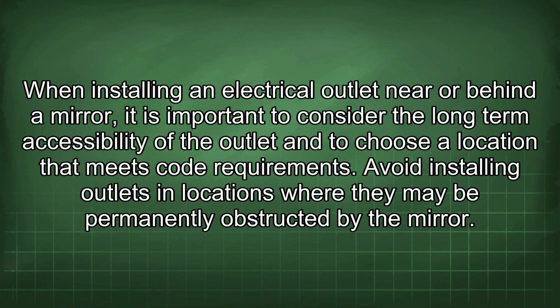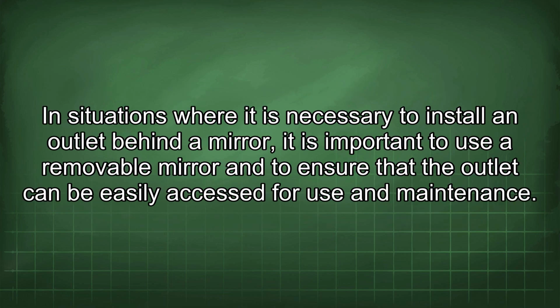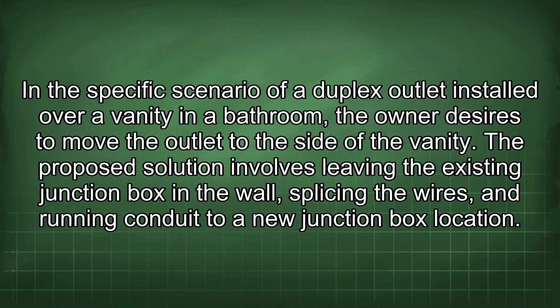Avoid installing outlets in locations where they may be permanently obstructed by the mirror. In situations where it is necessary to install an outlet behind a mirror, it is important to use a removable mirror and to ensure that the outlet can be easily accessed for use and maintenance. In the specific scenario of a duplex outlet installed over a vanity in a bathroom, the owner desires to move the outlet to the side of the vanity.